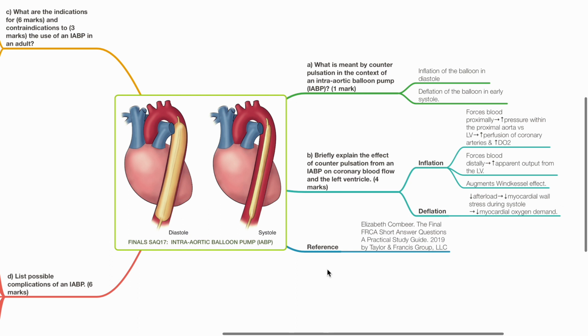Finals SAQ17 Intra Aortic Balloon Pump. A. What is meant by counter pulsation in the context of an intra aortic balloon pump? Counter pulsation refers to inflation of the balloon in diastole and deflation of the balloon in early systole.